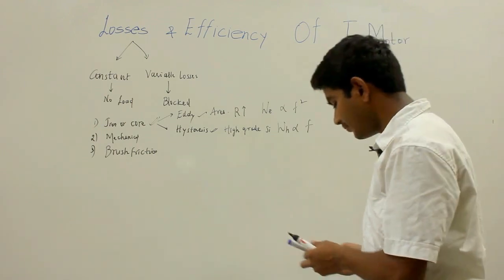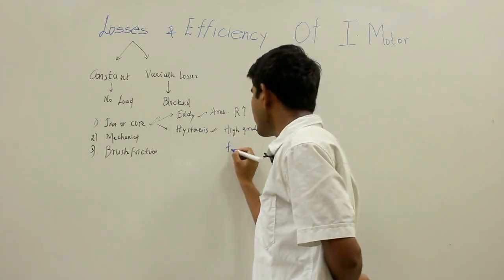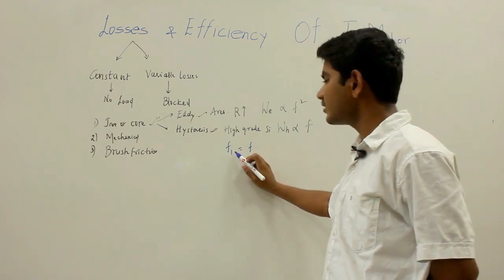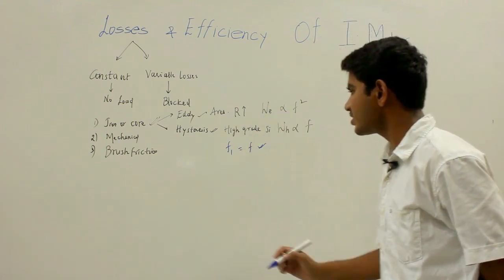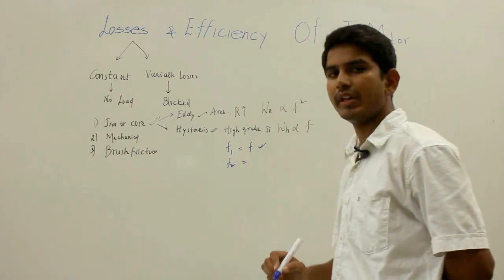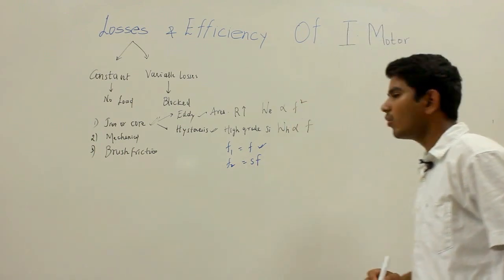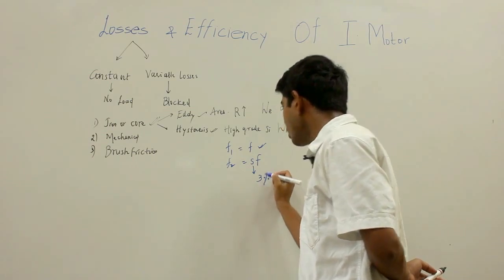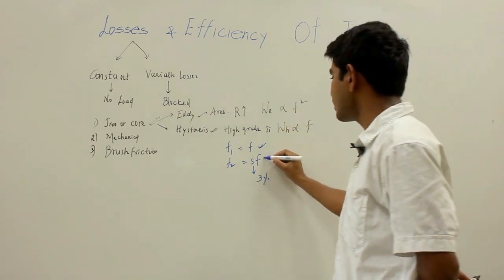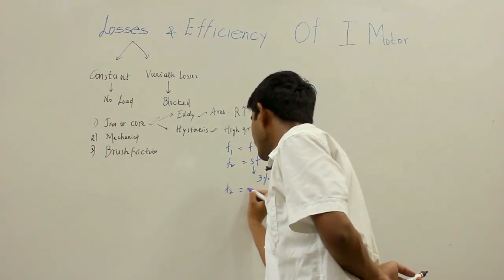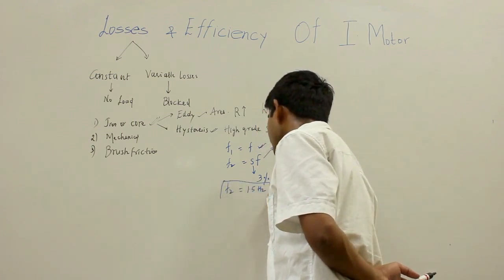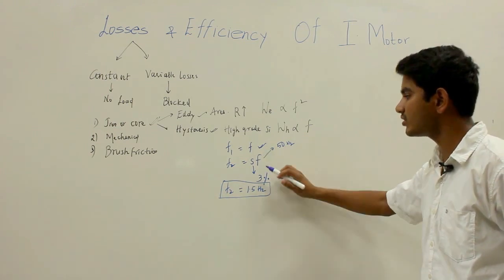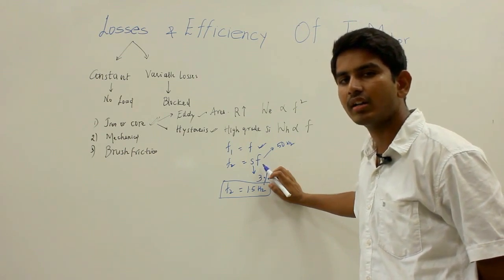The stator frequency f1 is equal to the supply frequency f. The rotor frequency f2 equals slip times the supply frequency f. Under normal working conditions, the induction motor slip is of the order of 3%. So if the supply frequency is 50 Hz, the rotor frequency will be 1.5 Hz. Since the frequency is very low, the rotor core losses can be neglected.